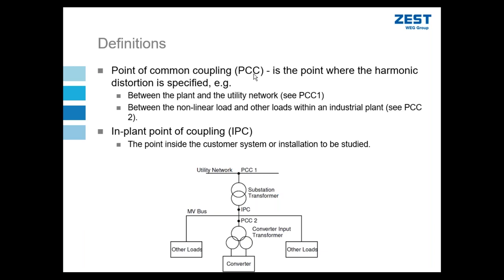This needs to be defined between the specifier of the harmonic limit and the equipment supplier. You're supplying equipment into the plant that could generate harmonics. Harmonic current does not tend to change through the impedance of the system, but the harmonic voltage does. The closer you get to the utility point, the point of common coupling between your plant and the utility, the less the effect a harmonic current downstream will have on your total voltage. Okay, so defining where the harmonic limit must be applied is quite important.